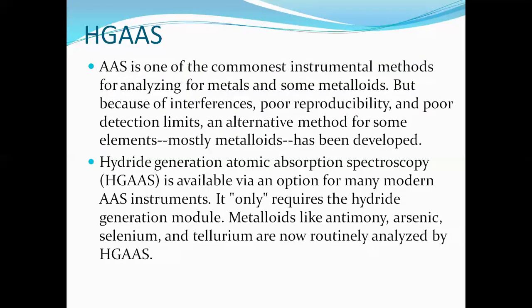Now we will discuss HGAAS — hydride generation atomic absorption spectroscopy. This is an advanced technique of AAS, mostly used for the detection of metalloids such as antimony, arsenic, selenium, and tellurium, which are not directly detected in their metal state. These metalloids can now be analyzed by hydride generation AAS.